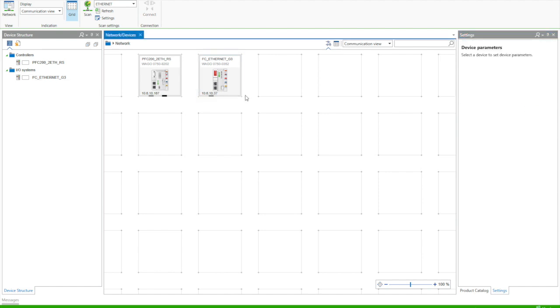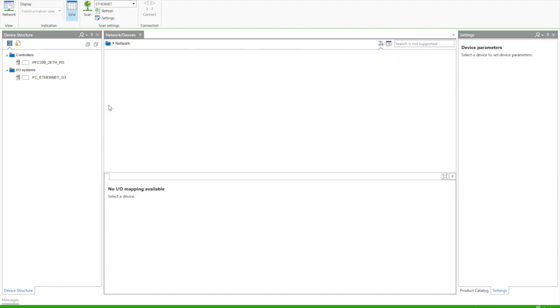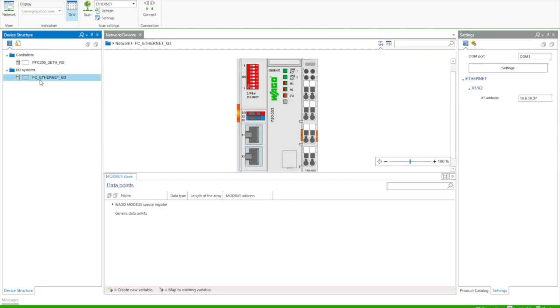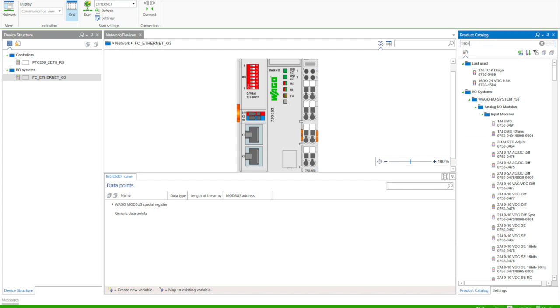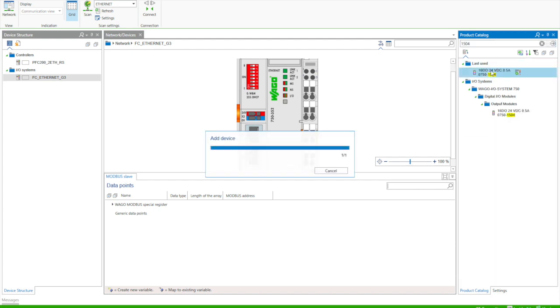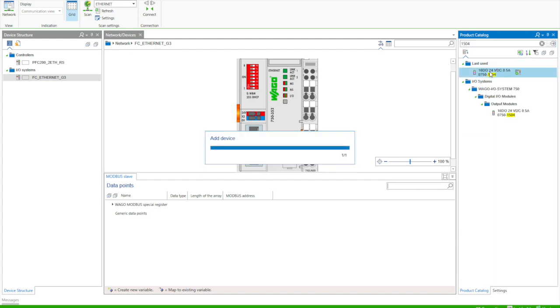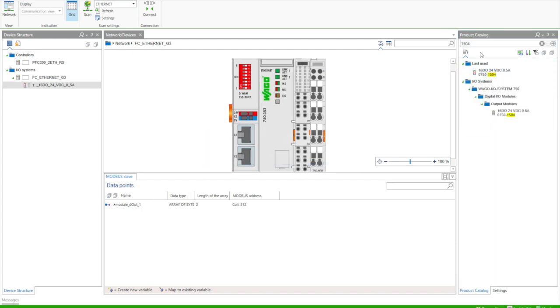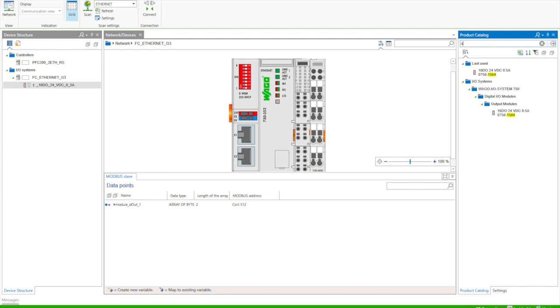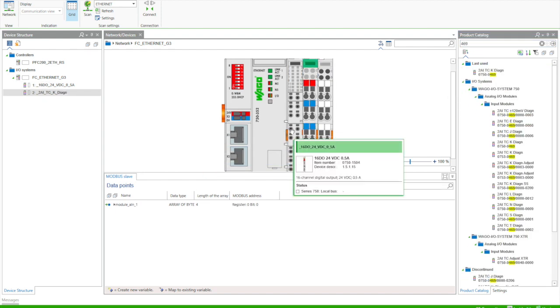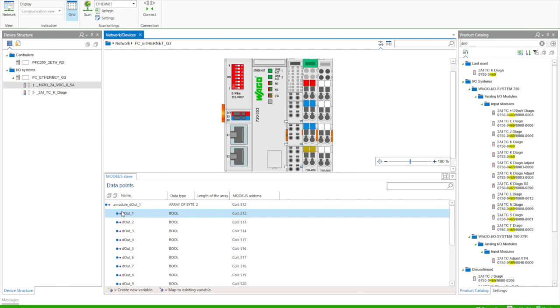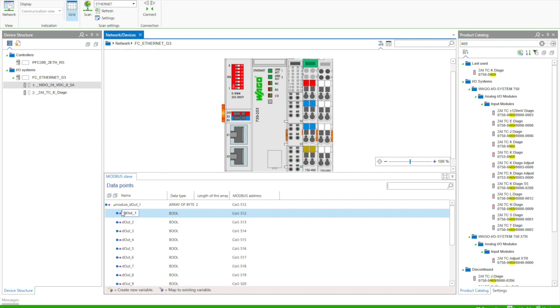Then we're going to double click on the coupler, and we're just going to add some I/O modules just like we would with local I/O on the PLC. So we can select from our hardware catalog. We've got a 750-1504 16-channel digital output module, and we also use a 750-469 two-channel thermocouple input module.